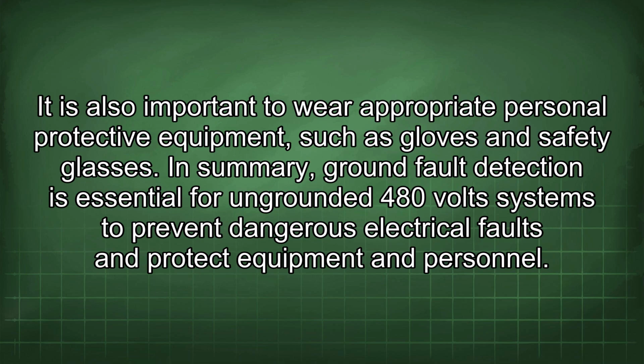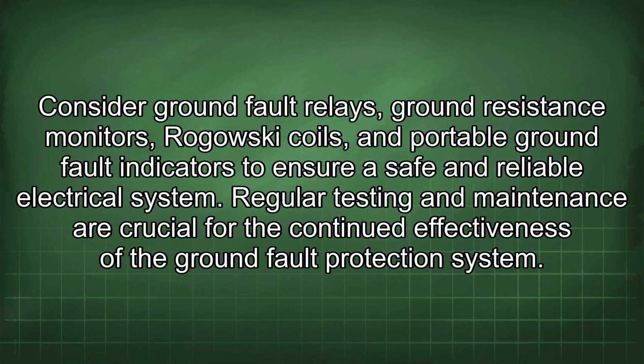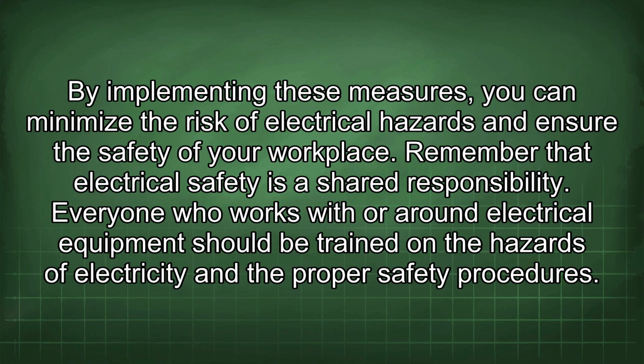In summary, ground fault detection is essential for ungrounded 480-volt systems to prevent dangerous electrical faults and protect equipment and personnel. Consider ground fault relays, ground resistance monitors, Rogowski coils, and portable ground fault indicators to ensure a safe and reliable electrical system. Regular testing and maintenance are crucial for the continued effectiveness of the ground fault protection system. By implementing these measures, you can minimize the risk of electrical hazards and ensure the safety of your workplace.